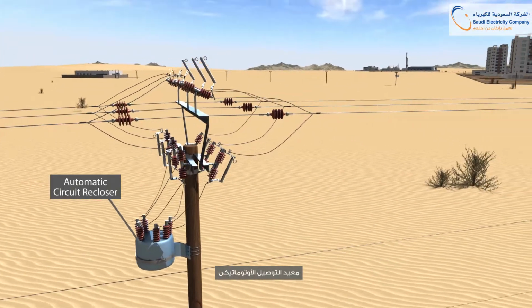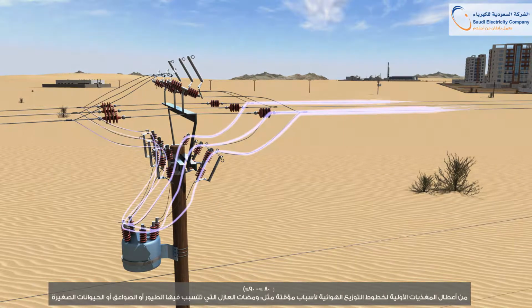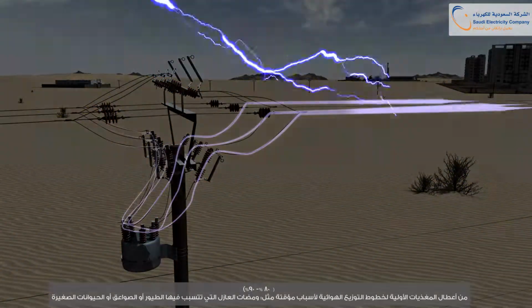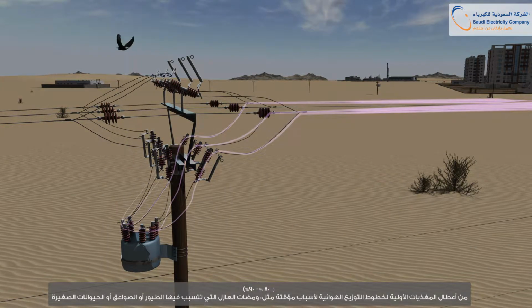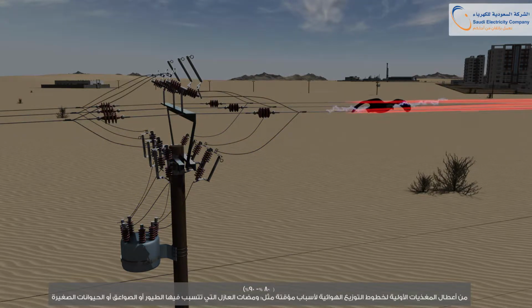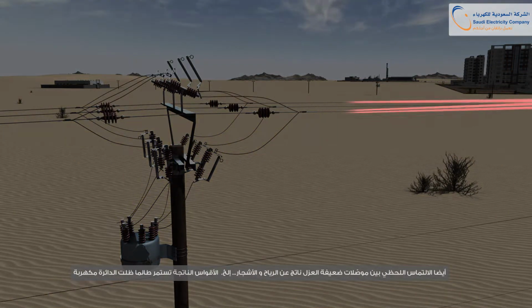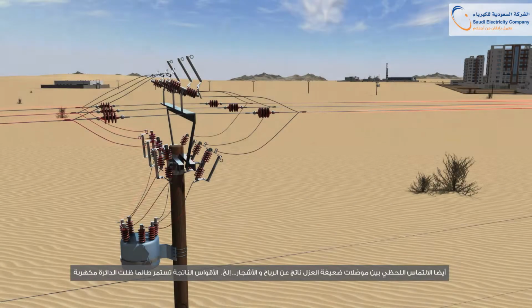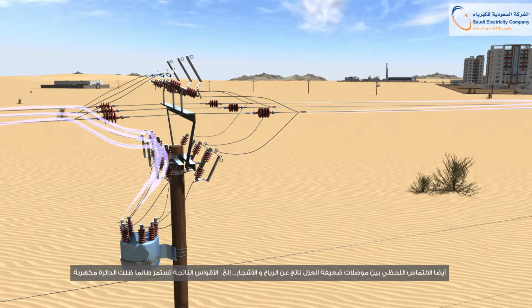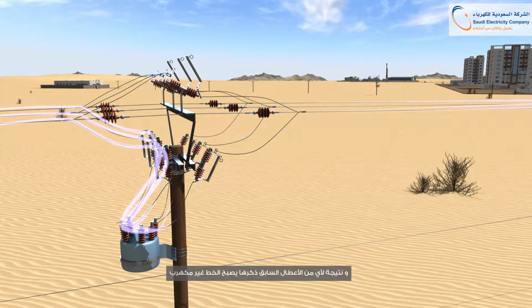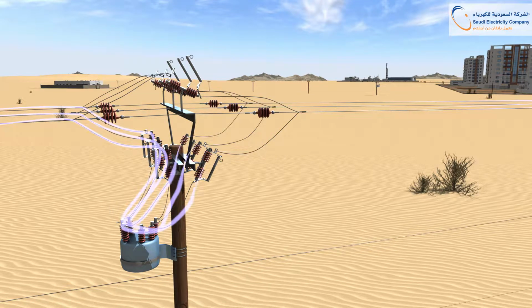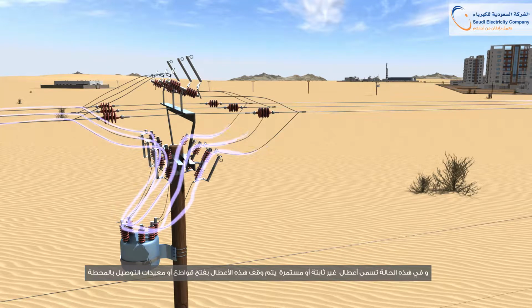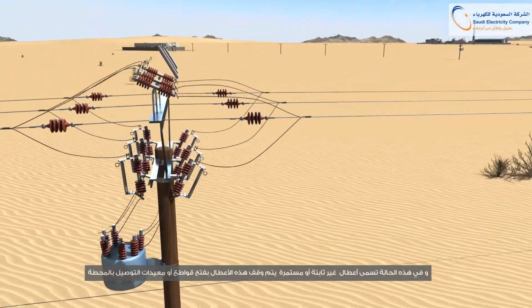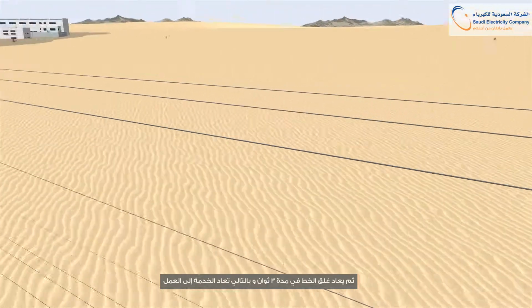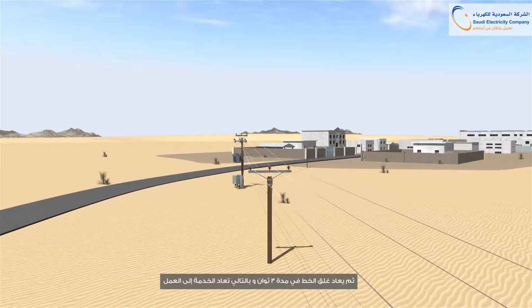Automatic circuit reclosers. 80% to 90% of the faults in distribution or primary feeders are from temporary causes. For example, insulator flashovers caused by lightning, birds or small animals. Also momentary contact between poorly insulated conductors due to wind and trees, etc. The resulting arcs frequently last as long as the circuit is energized. As a result of any of these faults, the line is de-energized, and in this case, the faults are known as non-persistent faults. The non-persistent faults are cleared by opening the substation breakers or the reclosers. The line can then be reclosed immediately, in 3 seconds, and the service is restored to all customers.